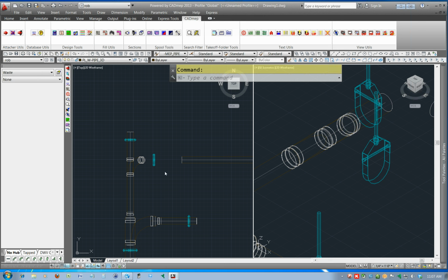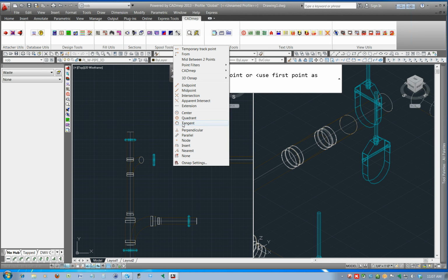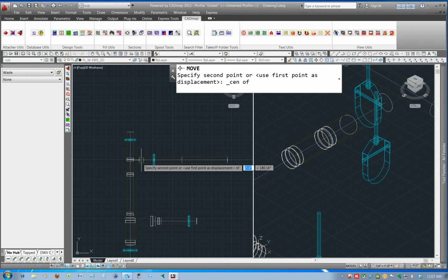That's another thing with pitch pipe. It's a bit of a pain when you're doing stuff like this, because when I rolled this, it's not in line with this anymore. Right, gotcha. The easiest way I found is to just move the pipe, because it's like a 1/16 of an inch off. It won't connect to the 1/16 of an inch, right? Yeah, that's a pain in the butt.